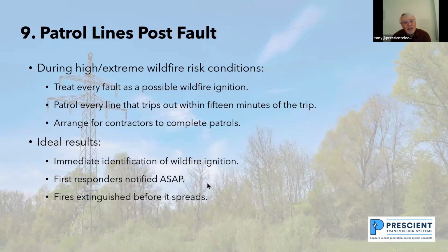And then patrolling lines post-fault. When you have higher extreme wildfire risk conditions, you have to treat every fault as a possible wildfire ignition, and you should patrol every line within 15 minutes of the trip. And that means that you have to arrange for contractors to complete the patrols.